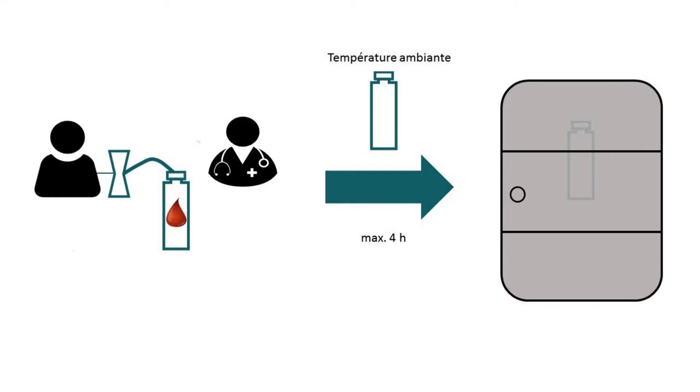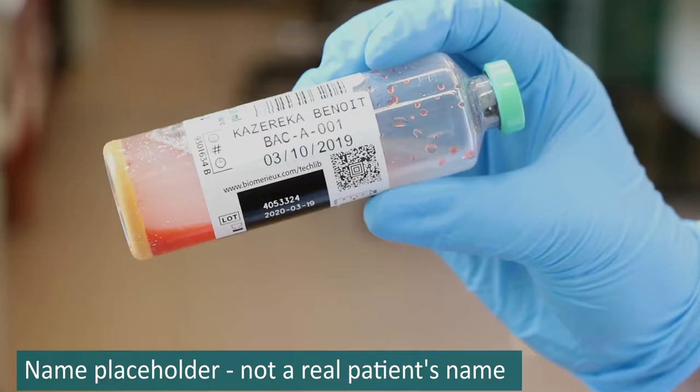After blood culture sampling, blood cultures need to be stored at room temperature until arrival at the bacteriology laboratory. The maximum delay between sampling and incubation in the automated BacT/Alert incubator is 4 hours, in order to avoid false negative results. Other systems may have other instructions.